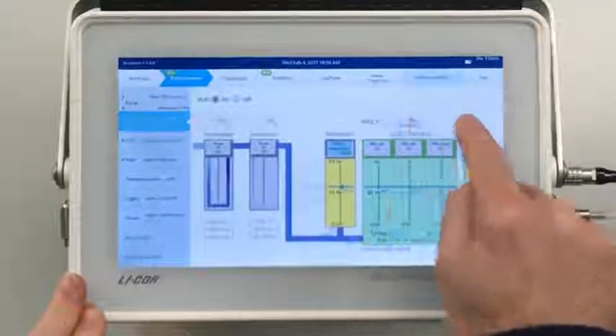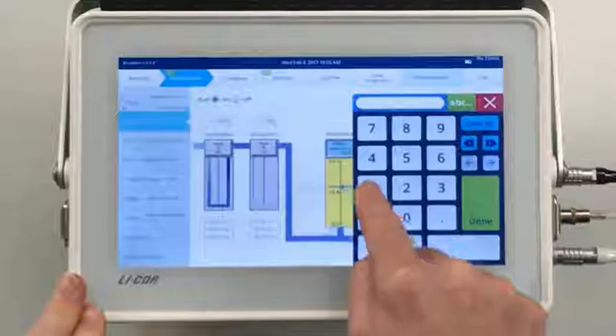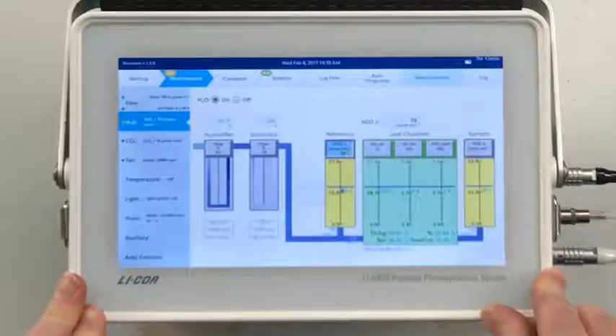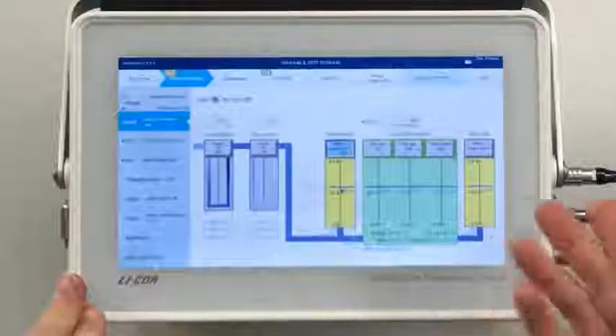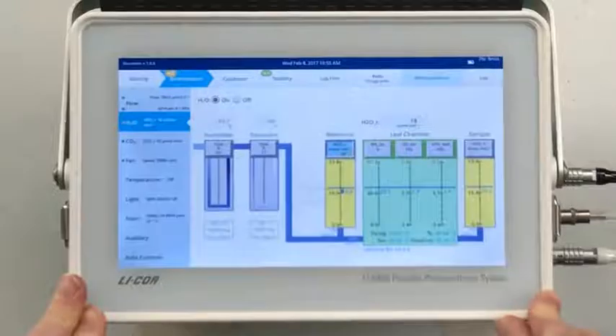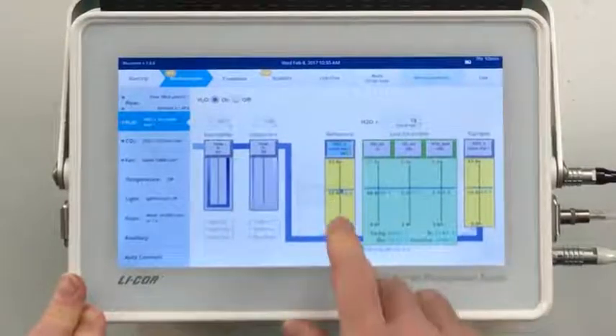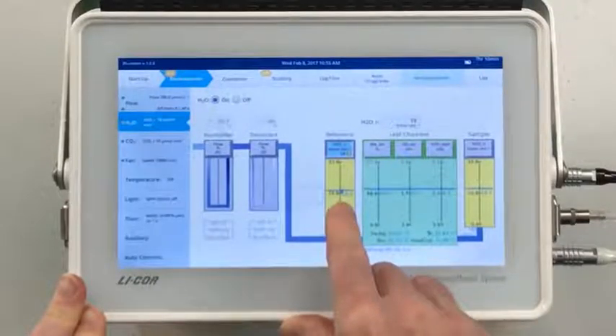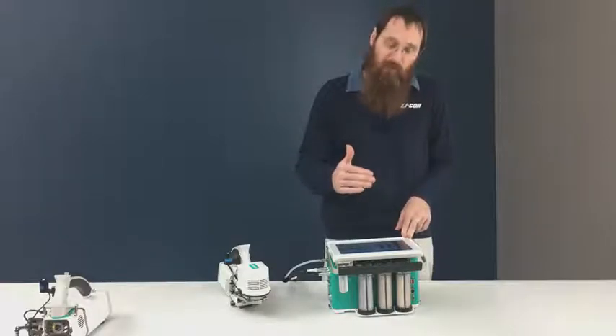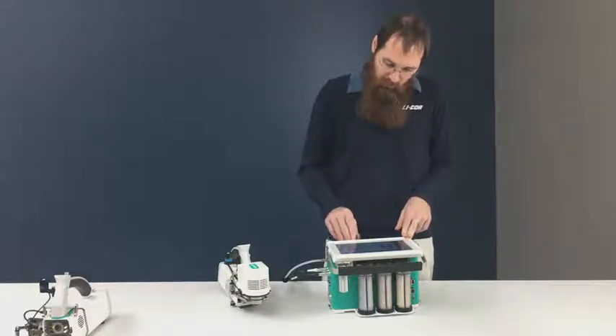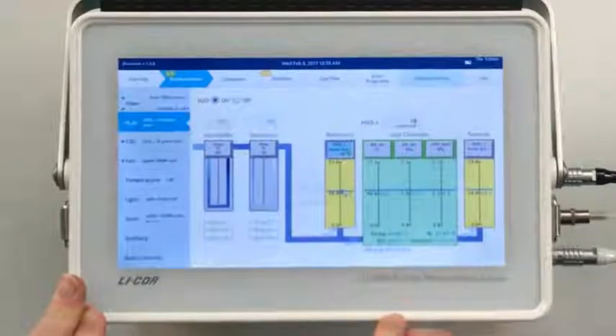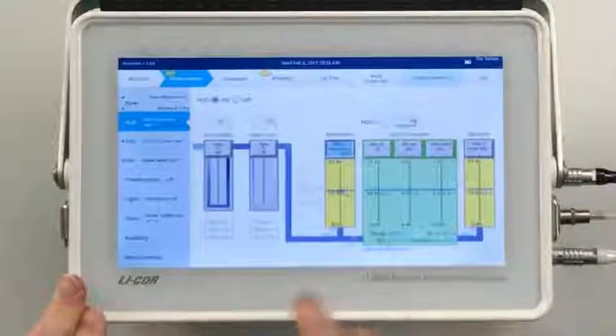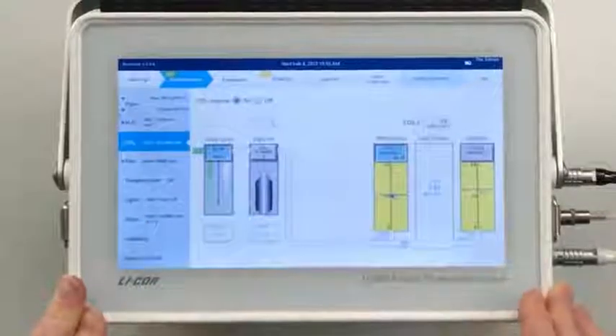You know, we can change these and the instrument will respond, right? If I want to drop the humidity down just a little bit, we'll set it to 18 millimoles per mole. And the instrument should fairly quickly respond to that change and drop the water vapor down. You can see these little bars moving on the scale to show us where the current concentration is. And we're at 18.